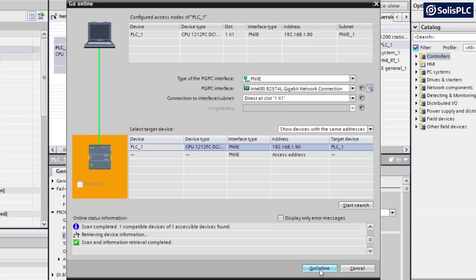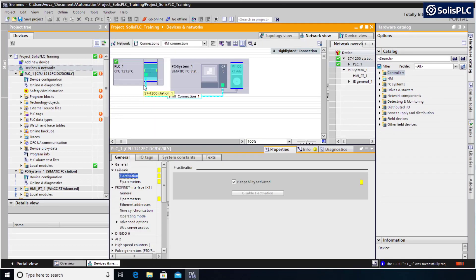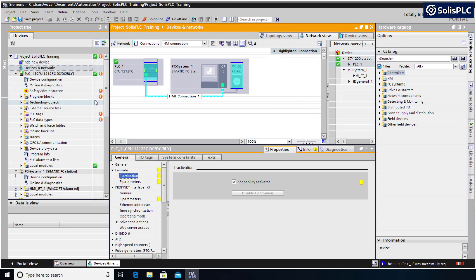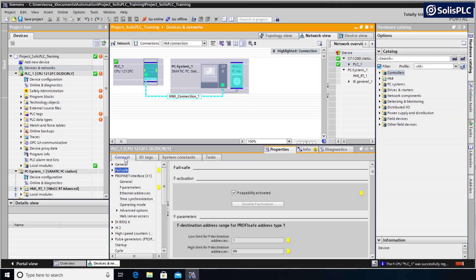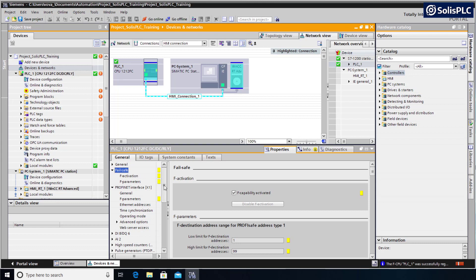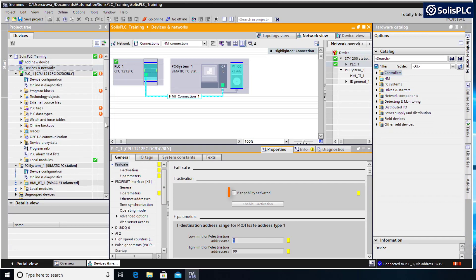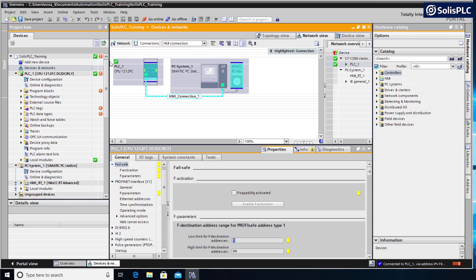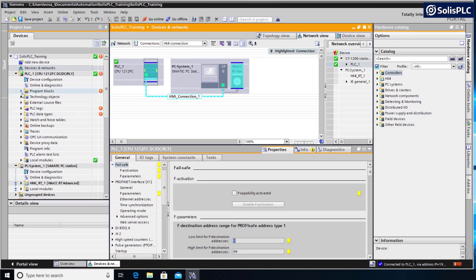If the search is successful and a device of the same type is found under the specified IP address, it will be populated in the table below. What we can do is press this Go Online button and the software will communicate with the PLC. The online confirmation for TIA Portal is going to be the highlighted Go Offline button, the top orange bar in the project, and a couple of warnings that you can see in the left-hand side that we'll need to take care of before we can download our project to the controller. Some of these options in this General tab are going to be slightly different if you're not working with a safety PLC.